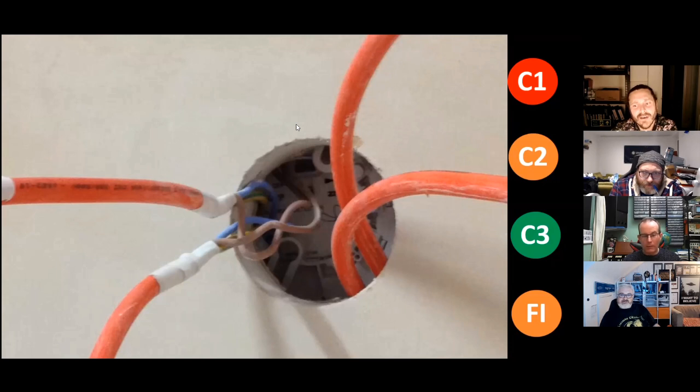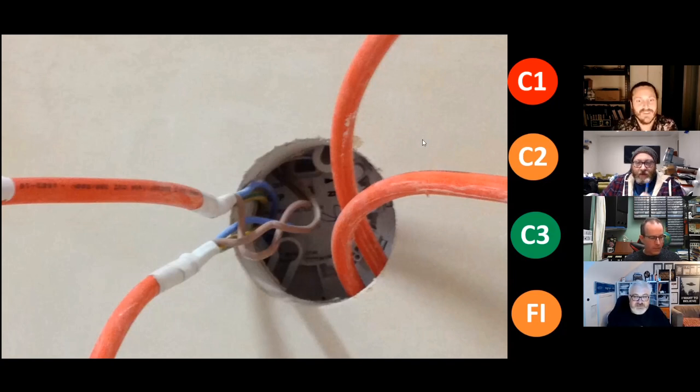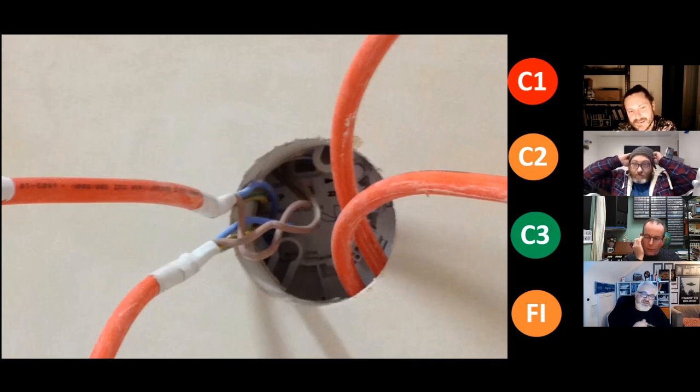As he said, they have plastered over the ceiling and used the base as a JB. So what he thinks there is a detector base, and they've just plastered over it, and it's just a joint box, essentially. Right, so we've actually got an old base, and we're looking from below up to it. Yeah. And it's been converted to a joint box. Yeah. So not an accessible connection. I mean, you do see this sort of stuff. I wouldn't want to, to be honest with you. That's just embarrassing. I mean, that's not a maintenance-free connection, is it? Better off just using a bloody 20-amp JB rather than one of them things, but...